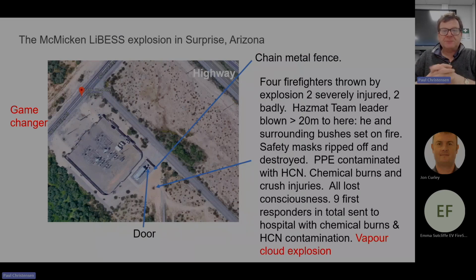This is the explosion in Surprise, Arizona, 2019. The fire service didn't know what it was, didn't know it was a lithium-ion battery system. There was no markings on it, and it was remotely monitored. The smoke alarm triggered and deployed Novec 1230, which is a liquid that vaporizes to form an inert gas.